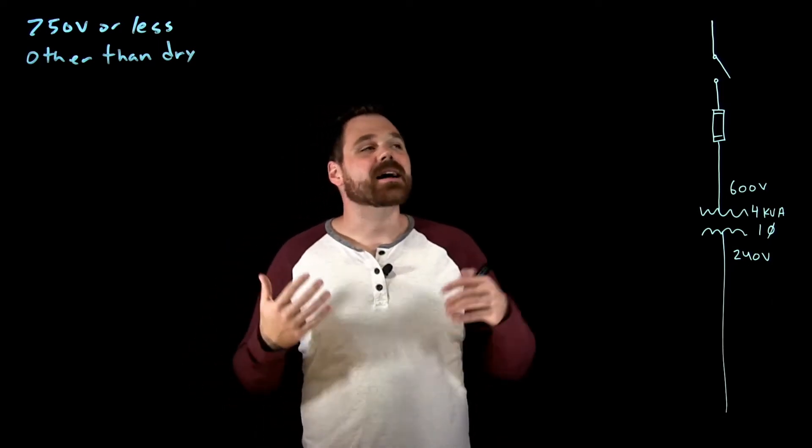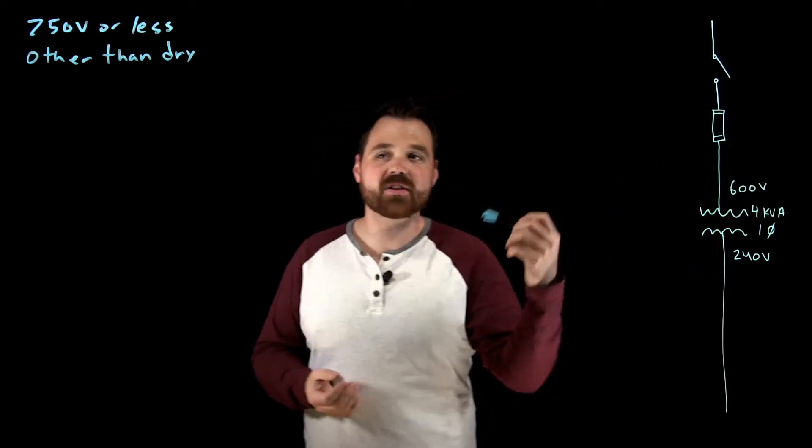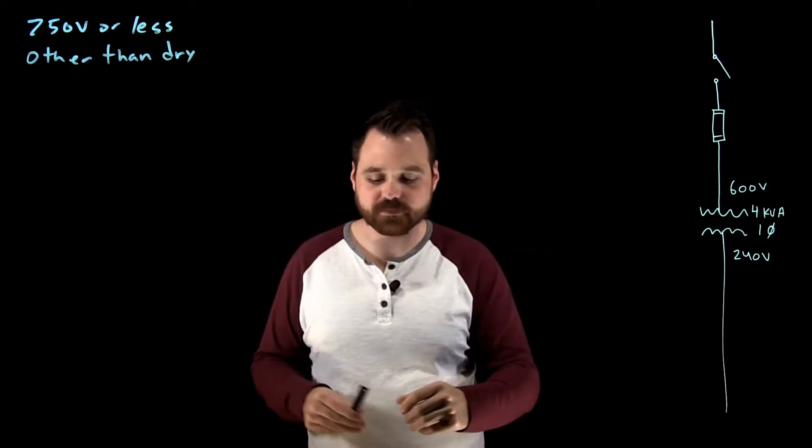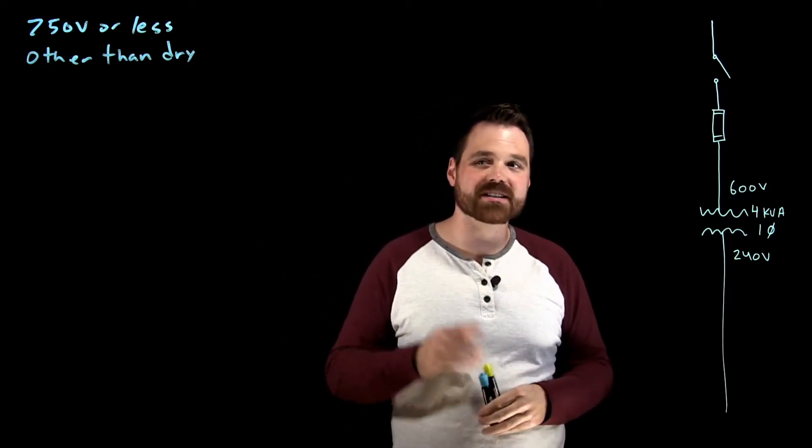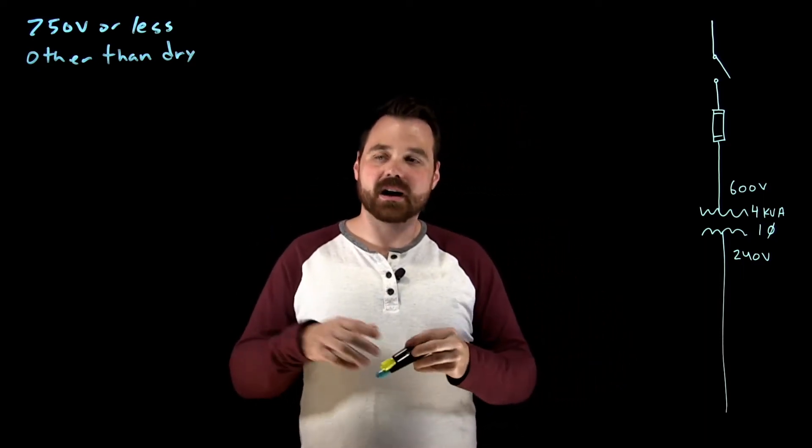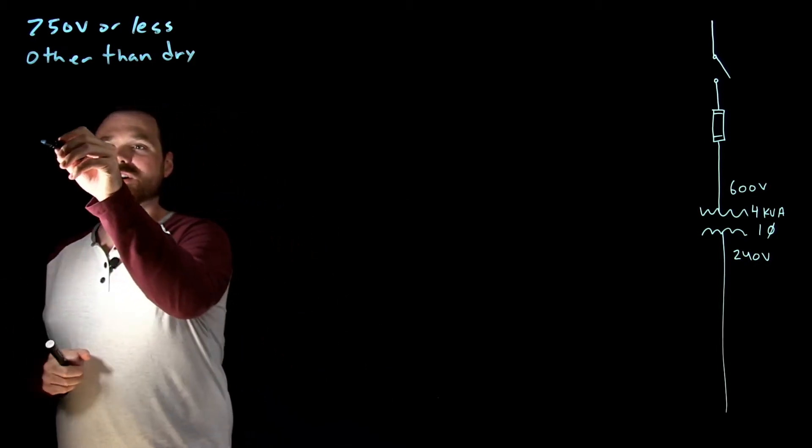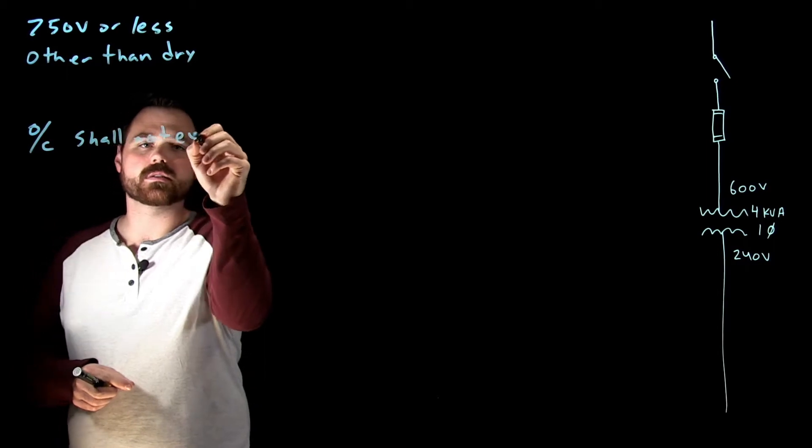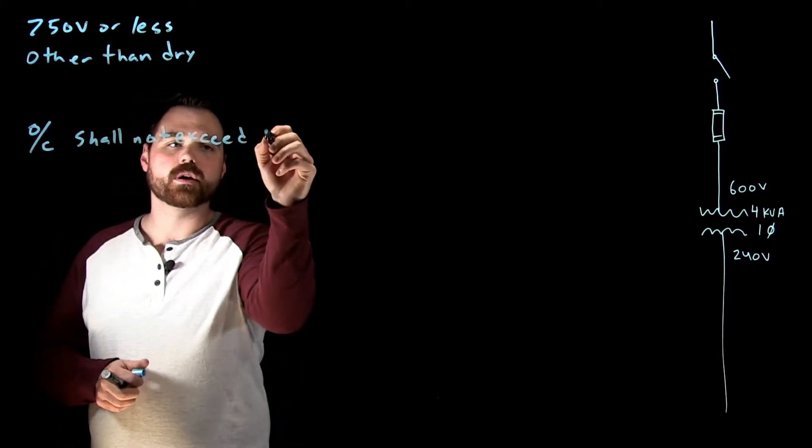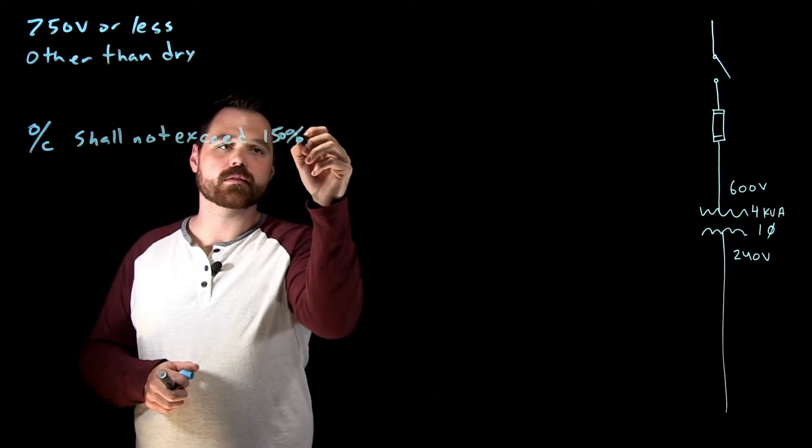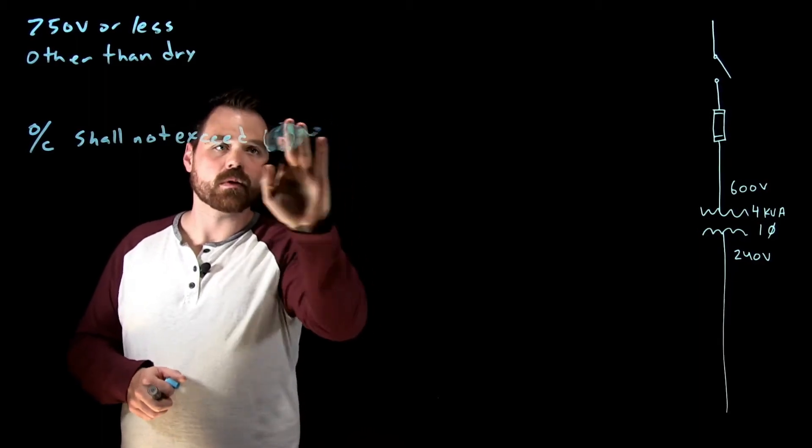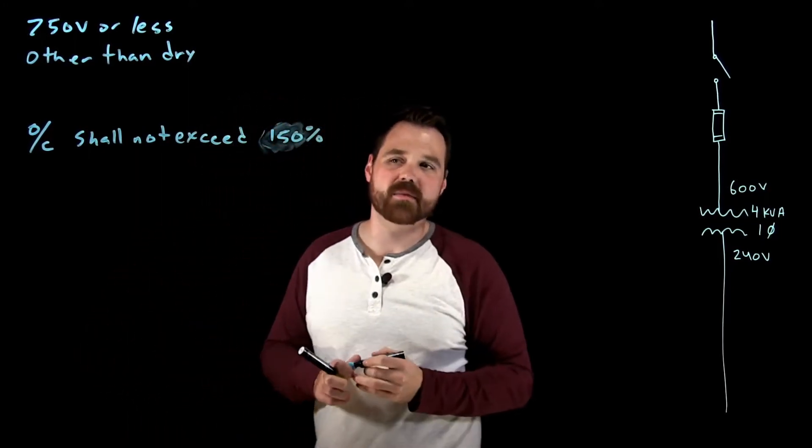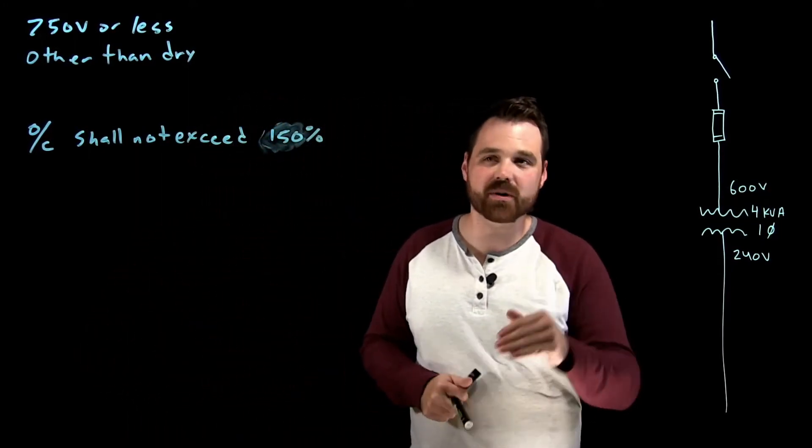It tells us that the primary overcurrent device shall not exceed 150% the rated primary current. Problem is we keep reading and it says, actually, so wait, let's take some notes here. It says OC shall not exceed 150% of rated primary current. But then it goes on to say, wait a minute.